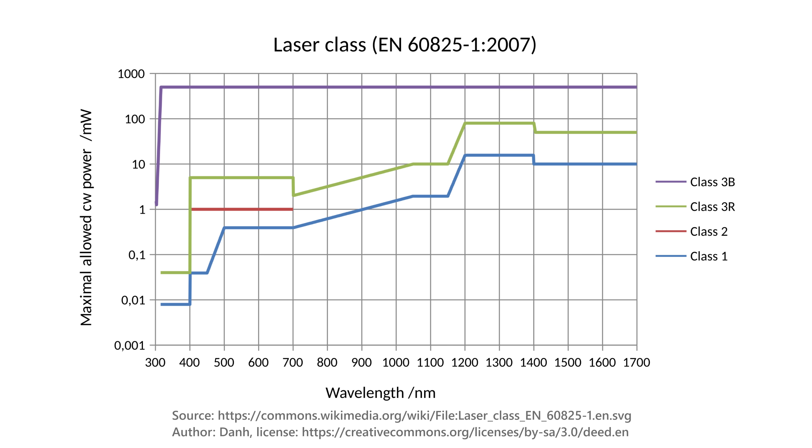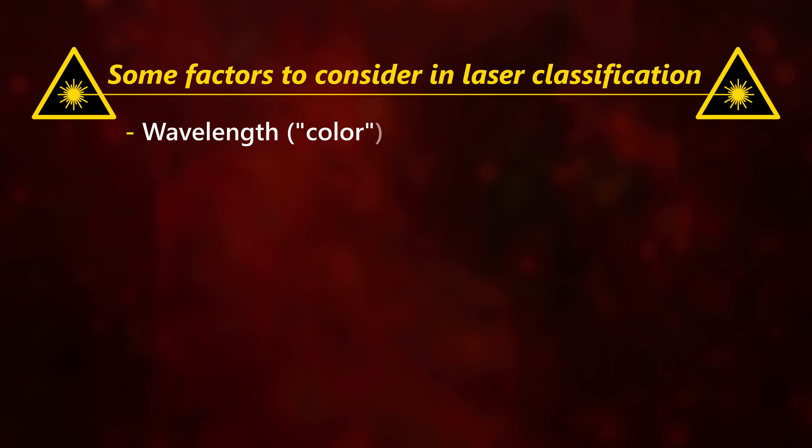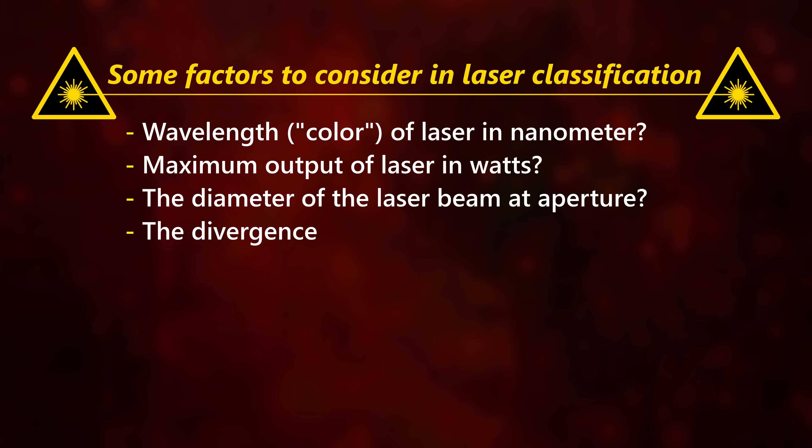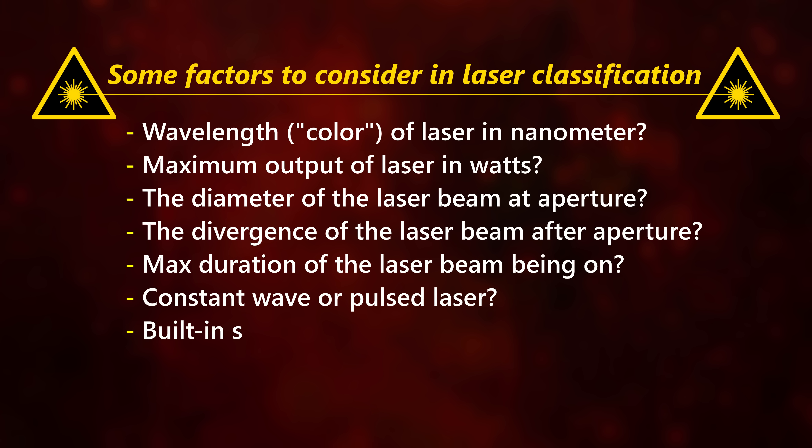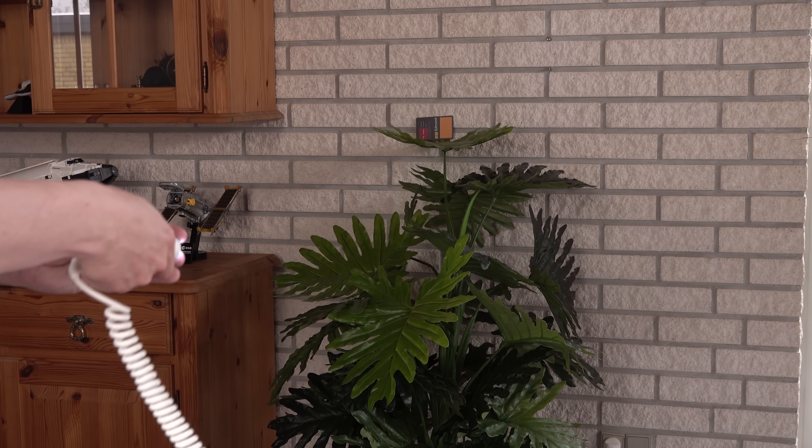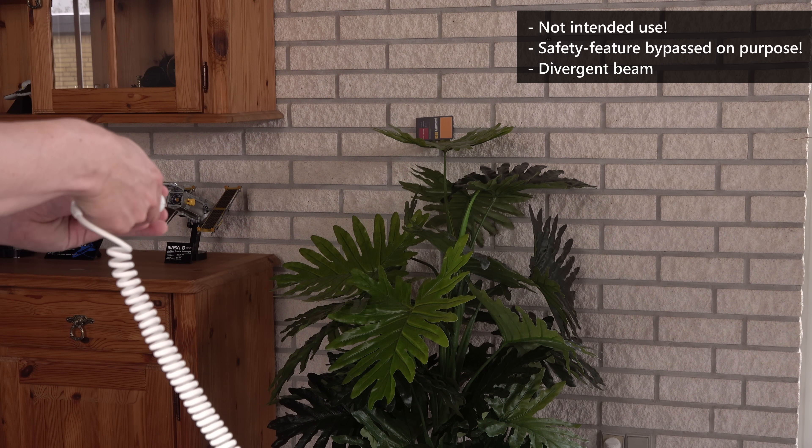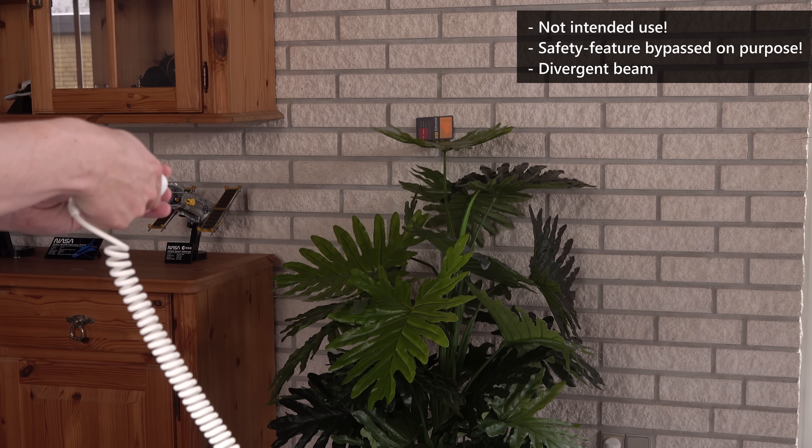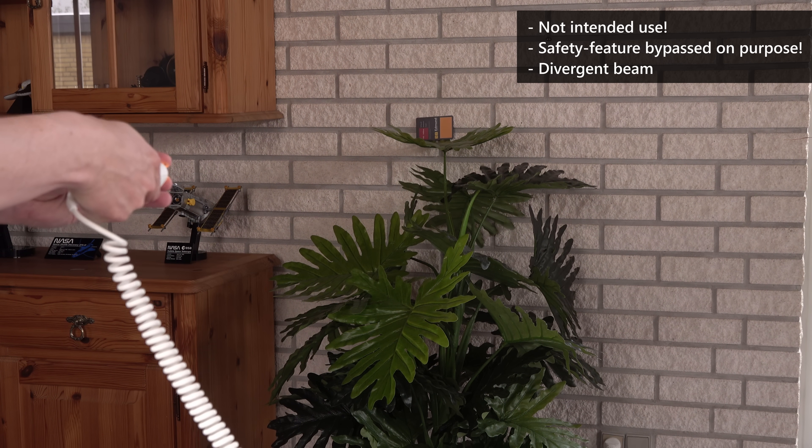This class 1 laser product seems to contain a class 3B laser based on wavelength and power alone. However, factors such as beam diameter divergence, duration and the intended use without bypass safety features also count in the classification. Is the embedded laser eye safe on the normal, intended reasonably foreseeable use? Probably yes.